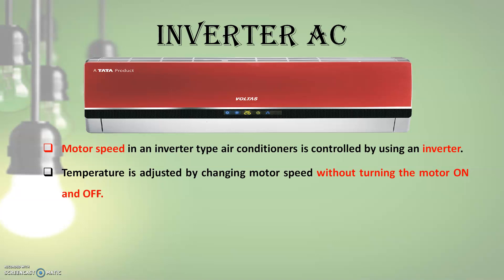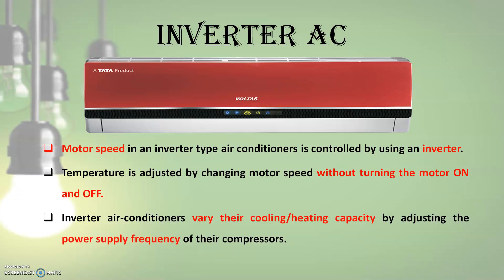An inverter type air conditioner varies its cooling and heating capacity by adjusting the power supply frequency of its compressor. The inverter does the function of varying the power supply frequency. It rotates the motor by switching the direction of electric current of the electromagnet, and the regulation of rotation speed is performed by controlling the switching speed.